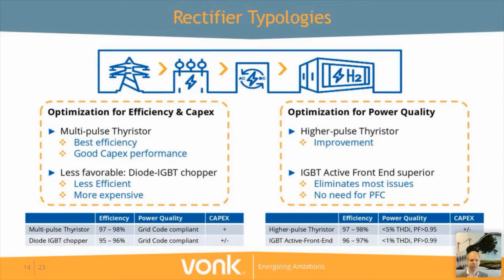The first one to look at is that of the rectifier topology. This is the single most determining item of choices within your power supply. Choices that you make for your topology have the most impact on the overall performance of your power supply. If you want to optimize for efficiency and capex, you want a lean and mean approach. There are two common options to achieve this. The first one is a multi-pulse thyristor solution, either at 12 or 18 pulses. We see this as the best option because it's got the best efficiency and good capex performance.